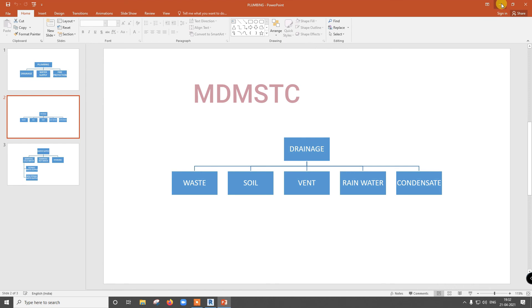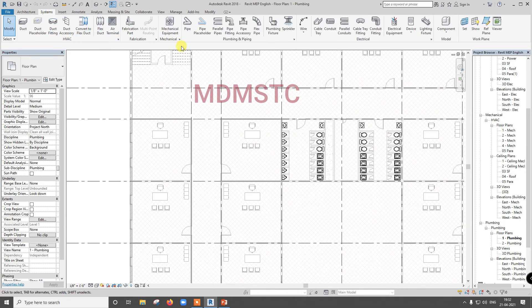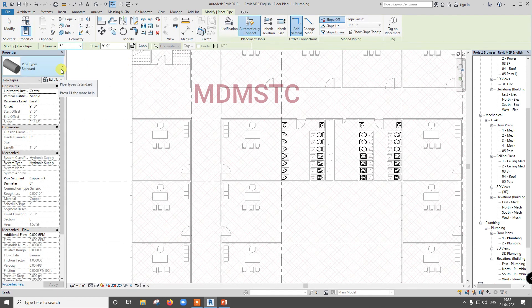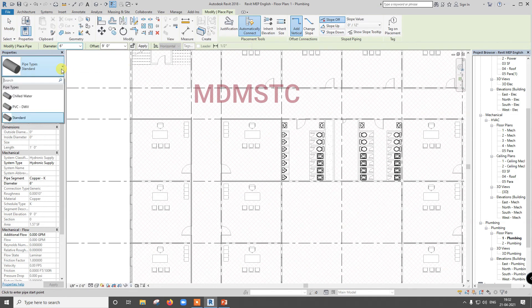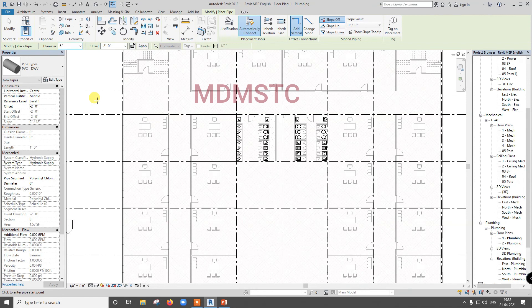Next we will go for drainage. Go to System, then Pipe, select pipe type under that PVC DWV — drainage water — select this. This is going below ground so I am going to give minus 2 feet, but this offset depends on your beams. Lower grade beams will be there under foundation — you should be careful that the pipe should not enter into the foundation. Your drainage pipe should go between the beams in the gap only.